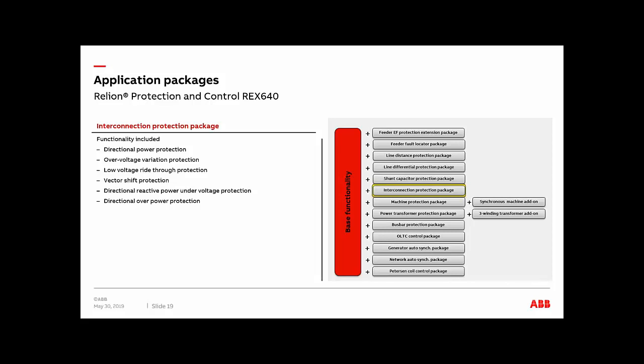In the case of our low voltage ride-through protection, pretty much this one is very similar to a 27 element, right? But in this case, it differs from the traditional three-phase undervoltage because it allows the grid operators to define their own low voltage ride-through curve for the generator. So they can decide where to ride through and where to disconnect the generation from the main grid. And I think I forgot to mention, we're talking here about microgrids. And this is mainly the reason why you will get the interconnection package, if you're protecting some sort of microgrid.